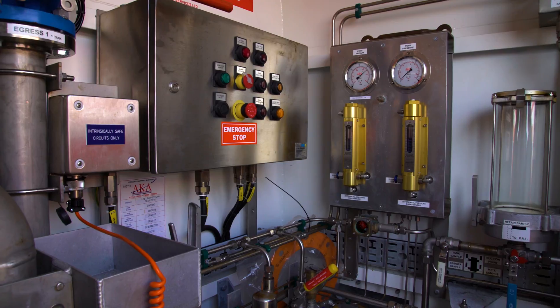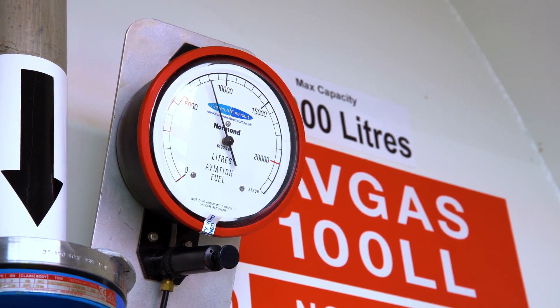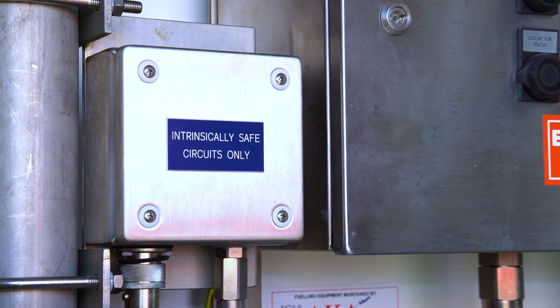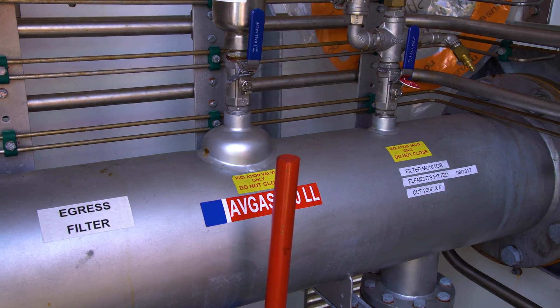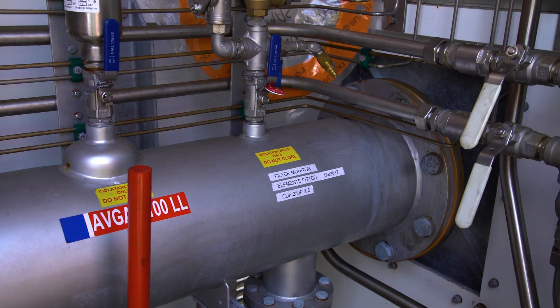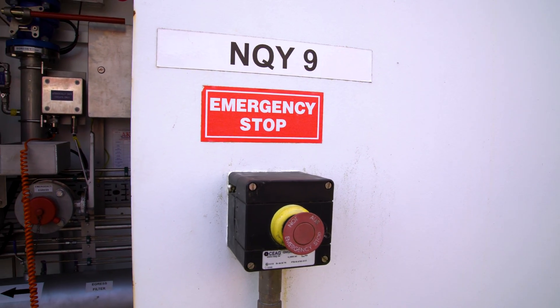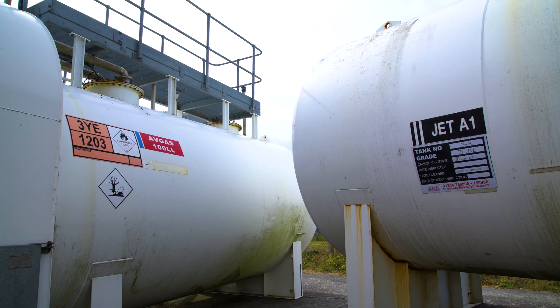As you can see here, we have various gauges, emergency stop buttons, and other test points. Also very important is tank capacity limits — making sure there is enough ullage space for the product being delivered. All electrical systems and mobile phones being used must be intrinsically safe. All the correct filters for Avgas must include inspection dates, change dates, and the addition numbers for the filters. Here we can see a nice example of a PRT tank, or product recovery tank. Emergency stop buttons should be checked on a quarterly basis, and on the side of the tanks you can see the correct signage with clear text of the inspection dates.